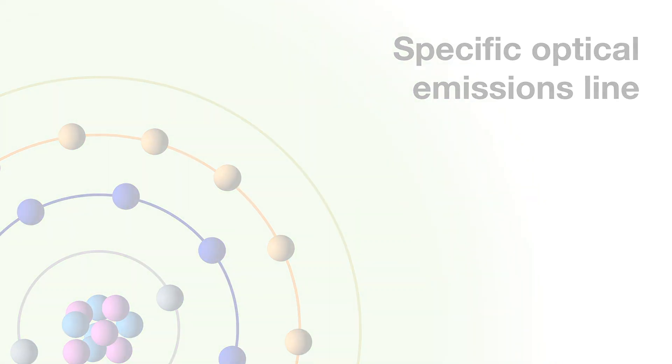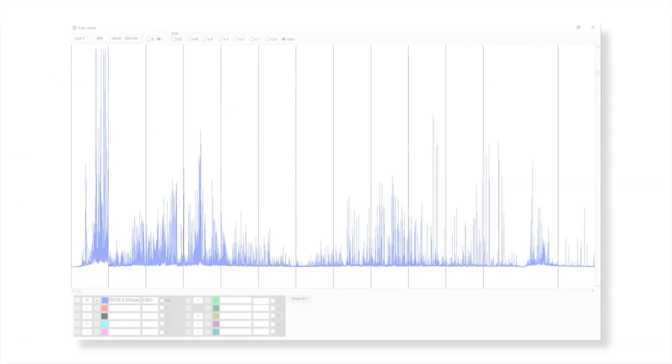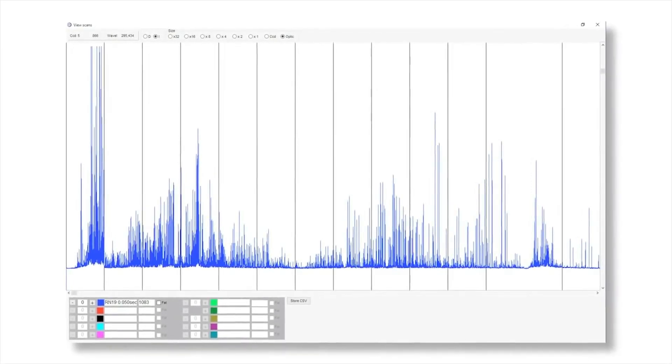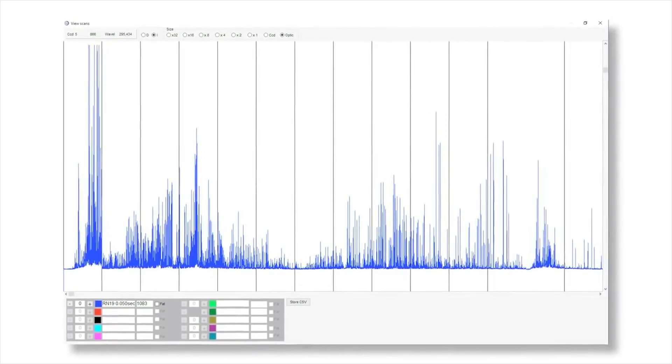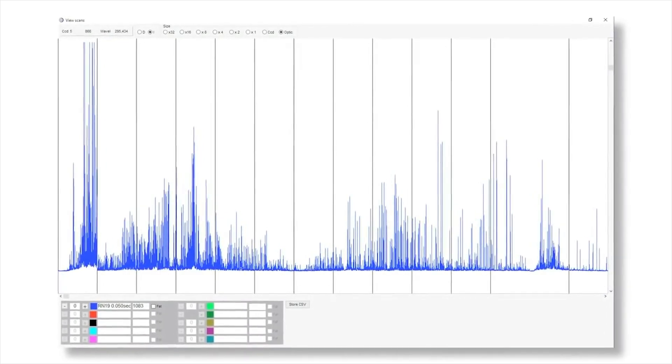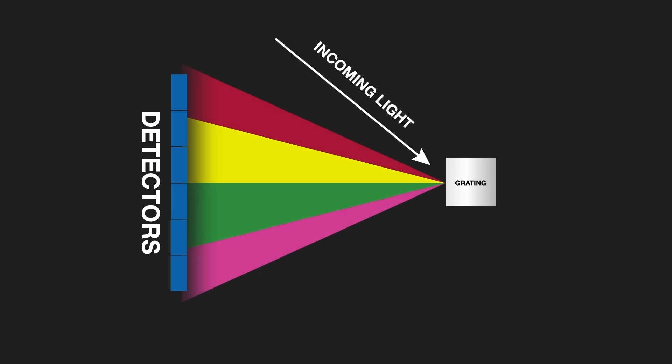For a typical metallic sample containing iron, manganese, chromium, nickel, vanadium, etc., each element emits many wavelengths, leading to a line-rich spectrum. For example, iron emits just over 8000 different wavelengths, so choosing the optimum emission line for a given element in a sample is important.